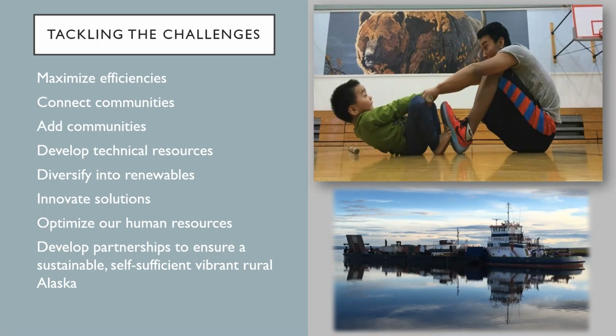We're actually at a practical limit in terms of the functionality of diesel generators, because the generators we use in the villages are very small, and as a result there's a limit to what can be done in terms of efficiencies. When you go into the larger turbines—3, 4, 5 megawatt diesel generators, even 11 and 12 megawatts like they have in the valley today—you can generate 16 to 18 kilowatt hours per gallon of diesel.